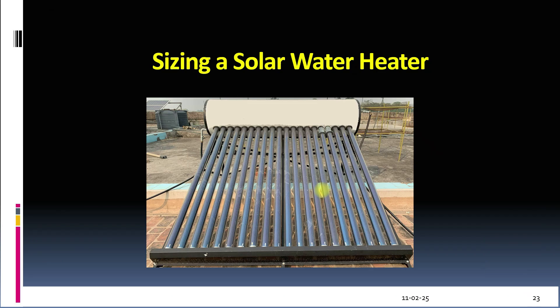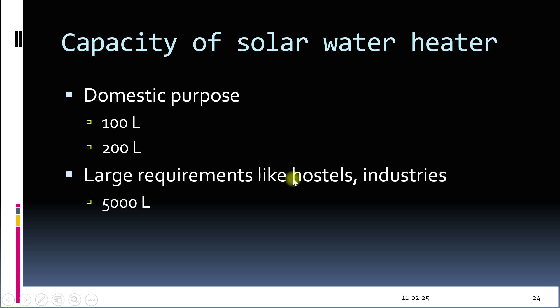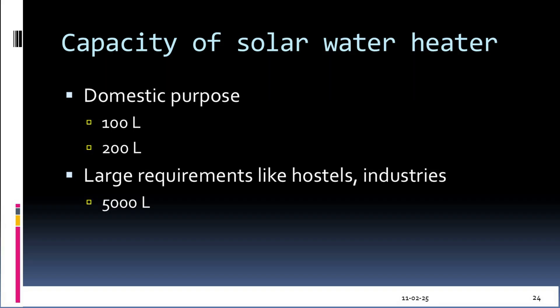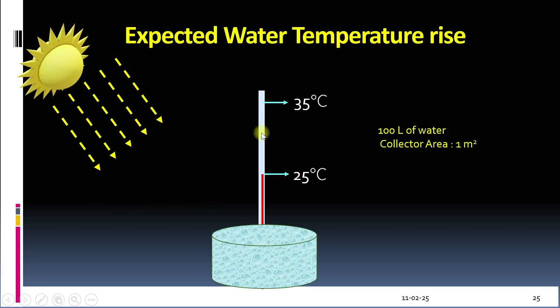The next big question is, what should be the capacity of the solar water heater? The size depends upon your specific needs. For most households, a capacity of 100 to 200 liters is sufficient for 4 to 5 members of the family. However, for larger installations like hostels or hotels, a capacity of 5000 liters or more is needed. So how hot will the water get?